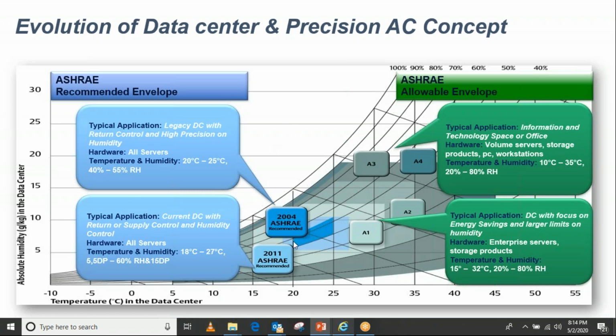Why was this approach coming? There was one more thing going on from ASHRAE. In 2004, ASHRAE released the recommended envelope, which was 20 to 25 degrees centigrade at the server's inlet. Then in 2011, ASHRAE changed it to 18 to 27 degrees centigrade. This was again a revolution in the industry. Those familiar with the data center industry know how much difference it makes to raise the temperature by 1 degree centigrade in front of the server. Even by 1 degree, you can achieve roughly 2.5 to 3% saving in efficiency.